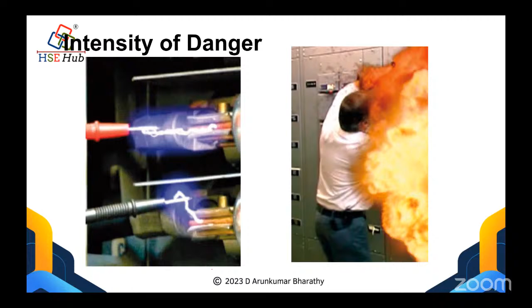Now what will happen? These are the things we saw: there are two arcs. When the connection is not proper, it will create some arc. When the two arcs, the red probe and the black probe, join together, it creates a short circuit. As electrical professionals, we know that where there is a short circuit, it has the least level of impedance, and where the impedance is least, current will flow. But in this case, along with the current, it also carries energy. The result is arc flash. You know that, right? So on this point we have to educate our team.